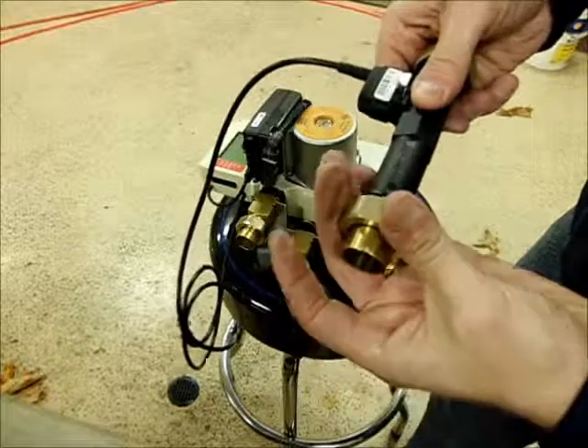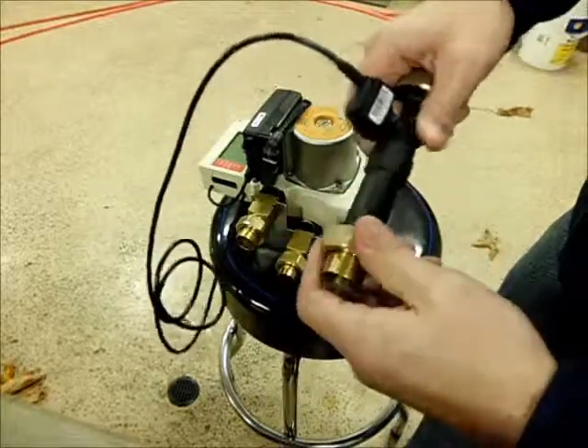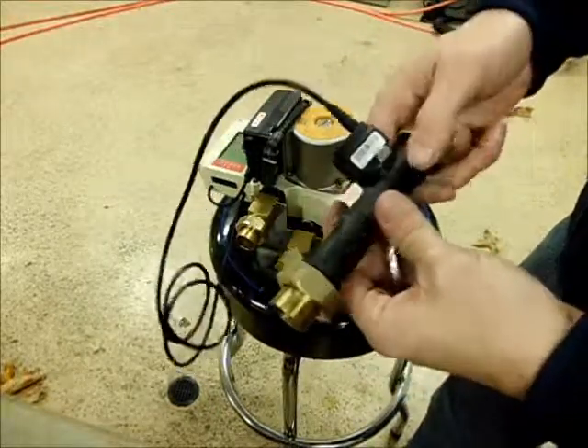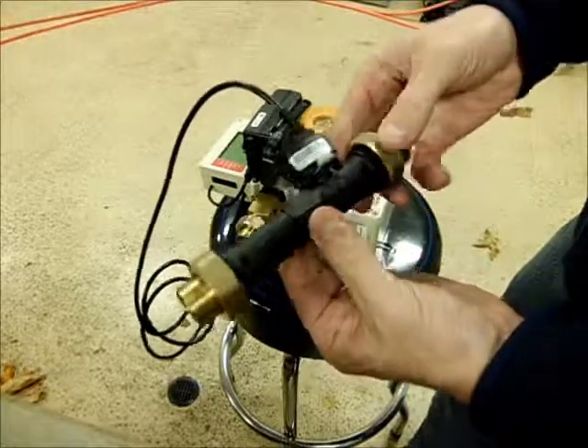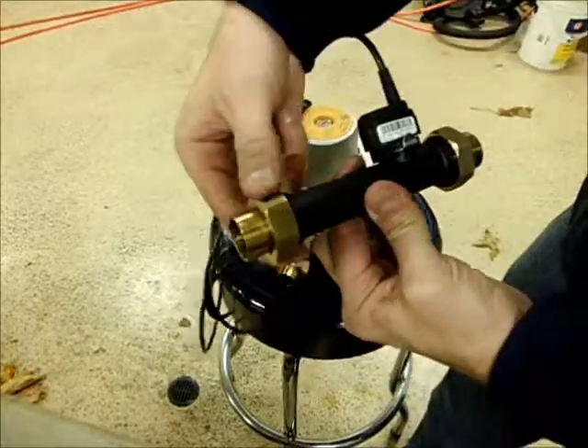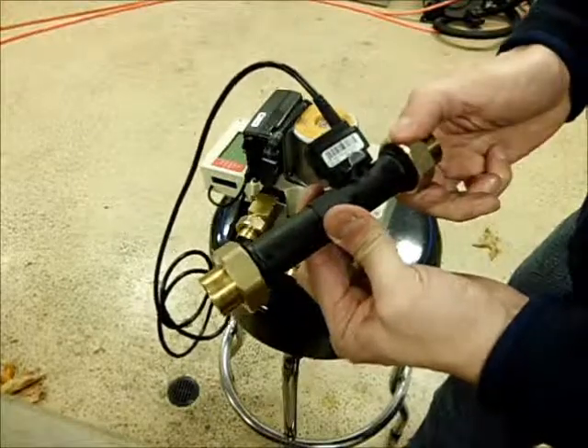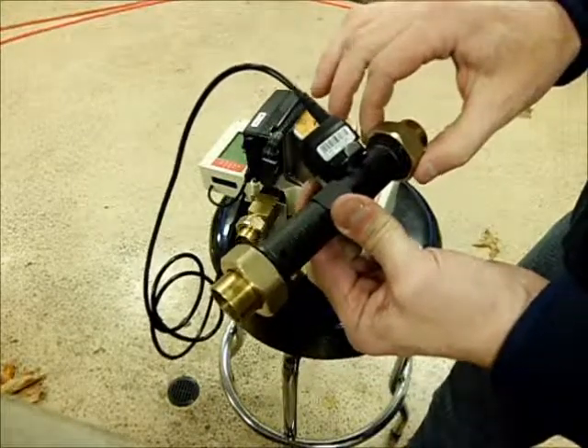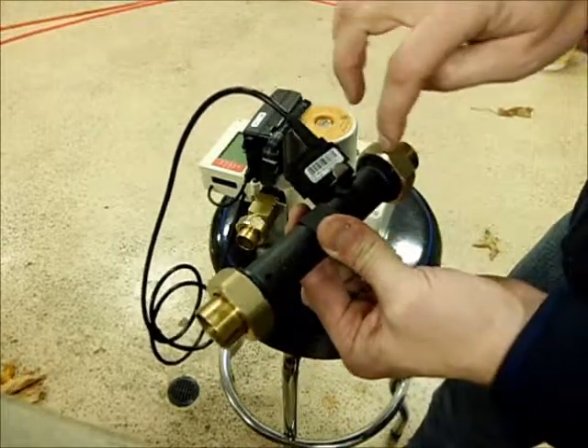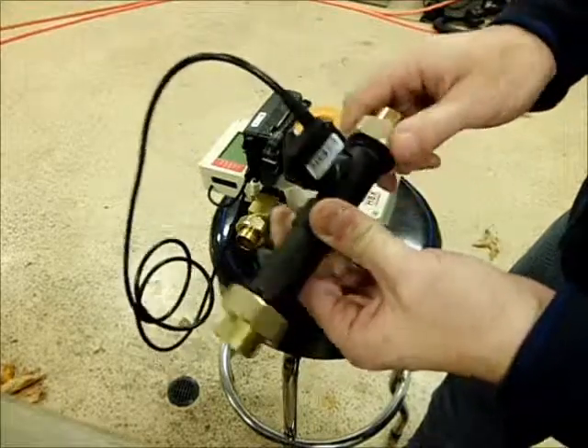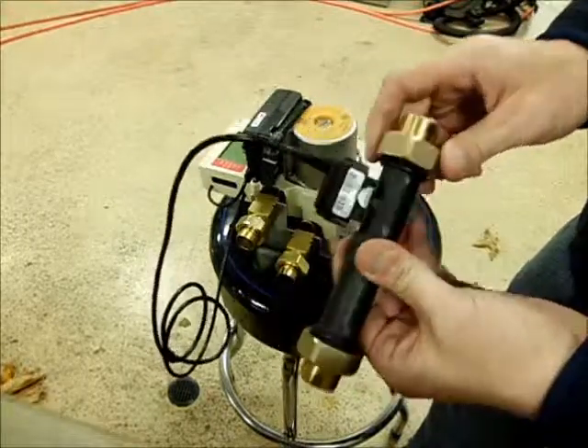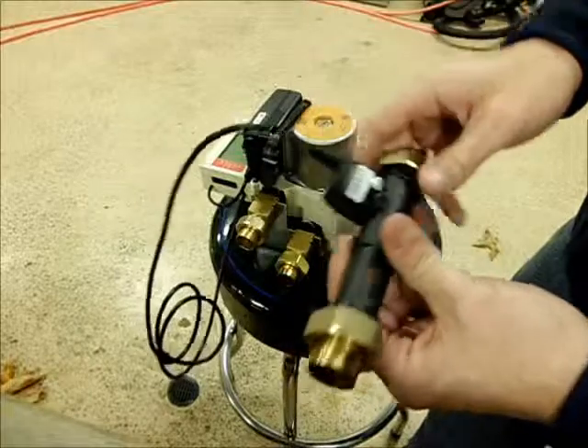And then you mount your brass fitting to that, tighten it up. And when you're tightening these up, make sure you use a wrench to hold the flow sensor here, and then tighten this nut and tighten this nut. You don't want to go over tight on these, because remember, this is going brass to a plastic fitting, so don't go crazy on these. Just get it so it's not leaking, and then a little bit more.